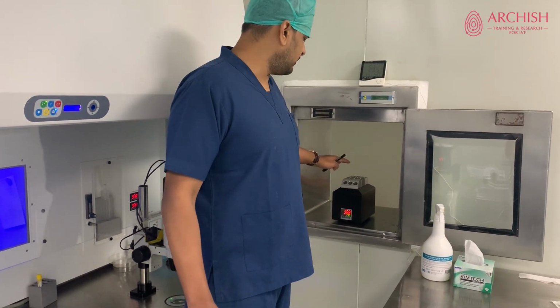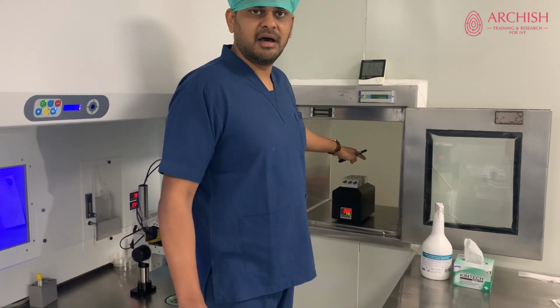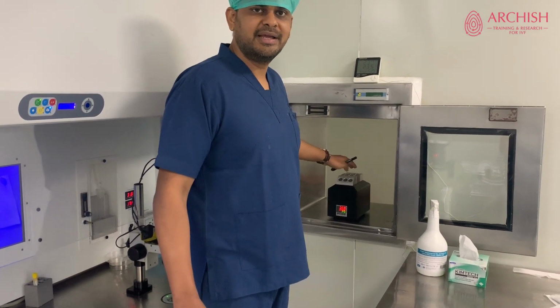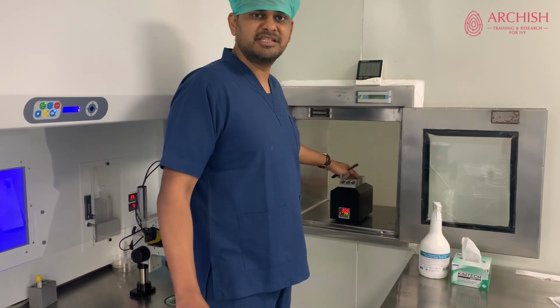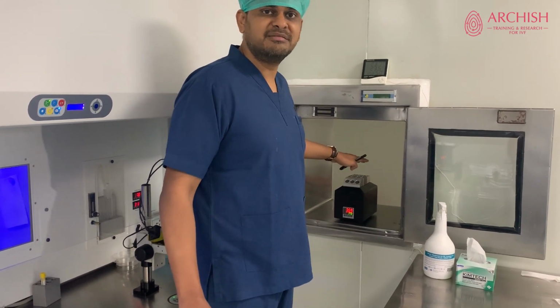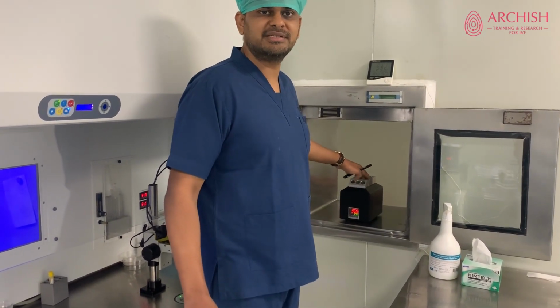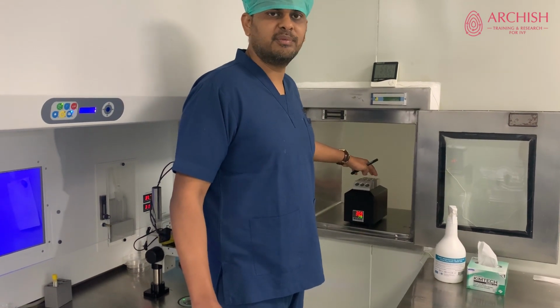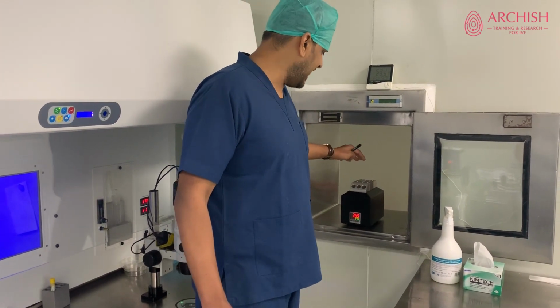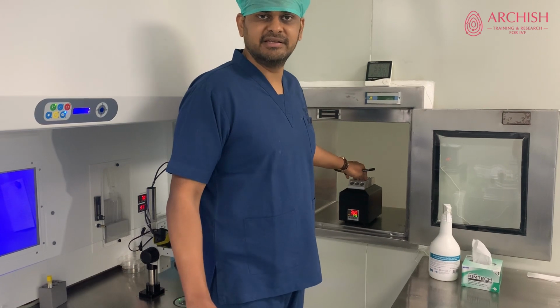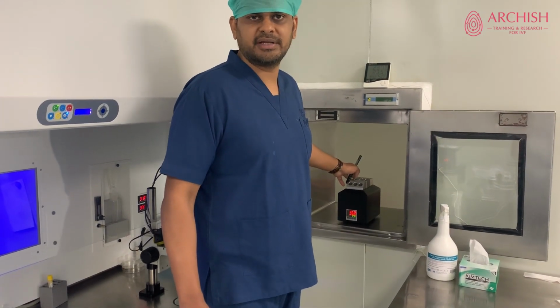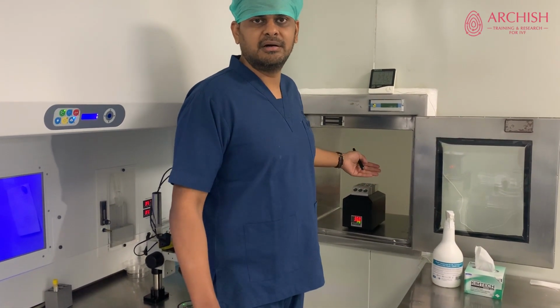Once the pickup is getting done, the nurse will collect the fluid and keep it in test tubes in this particular heating rack. It's important that the blood which is there inside these tubes along with the fluid has to be at 37 degrees. Otherwise it will just clot and you are going to lose out on the important eggs.